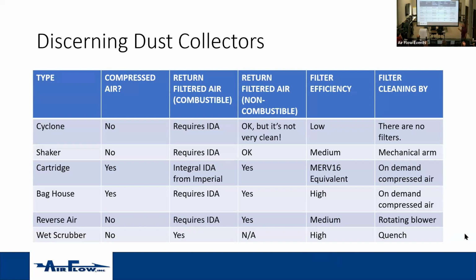On a shaker, sometimes a cyclone and a shaker will be combined together. A shaker has no compressed air. It uses a mechanical arm or a device that shakes the bags themselves off to clean them. It also requires IDA. Pretty much anything returning to the space has to stop that deflagration from going back into the building. You can return it, not a problem, coming off a shaker. Filter efficiency is medium. You can get real expensive and put some real expensive filters in. They catch everything, which means you change them more often. And the filter cleaning device, like I said, is the mechanical arm.